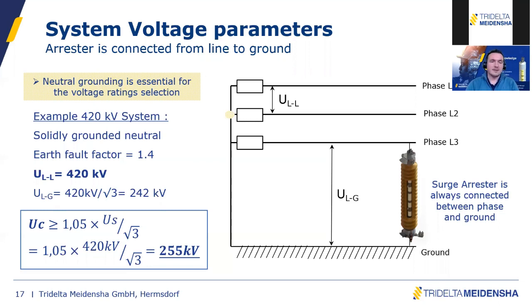So the maximum phase-to-phase voltage is 420 kV, and if you're not a specialist, the ratio between phase-to-ground and phase-to-phase is the square root of 3. So the maximum expected voltage phase to ground for a 420 kV system is 242. And as you know, for such applications, the surge arresters are always connected from phase to ground.